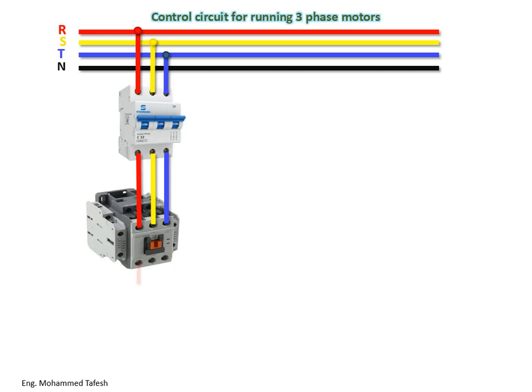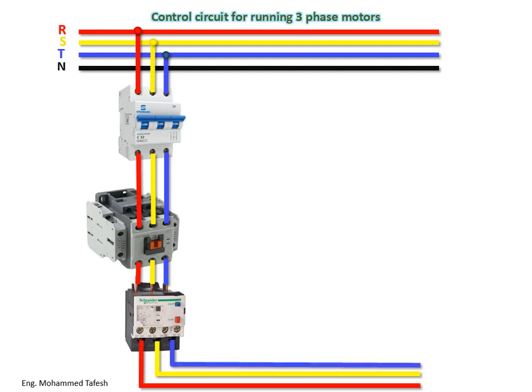From the output of the contactor, we connect the overload relay. As explained previously, there are two types of overload connections — it can be connected directly to the contactor or through other connections as shown in the presentation. In motors, certain conditions can cause a high current to be drawn. One reason is a drop in the supply voltage, which causes the motor to compensate by drawing more current, increasing the ampere percentage inside the motor and potentially leading to the burning of the thermal coils due to excessive heat.